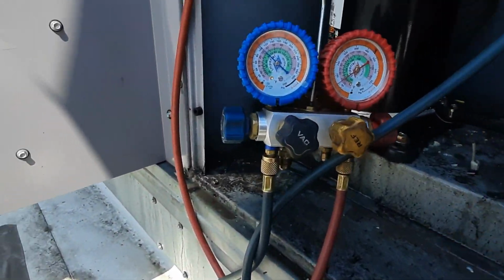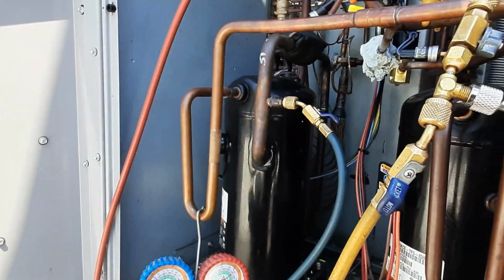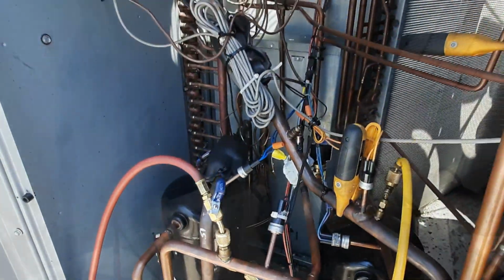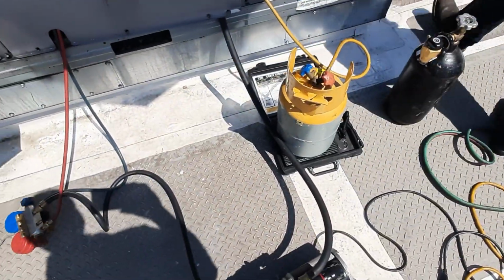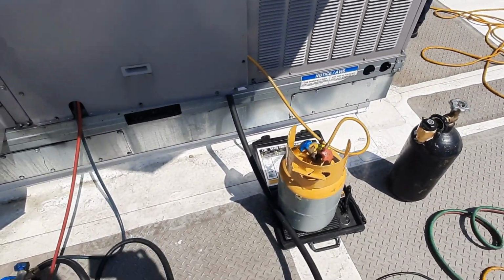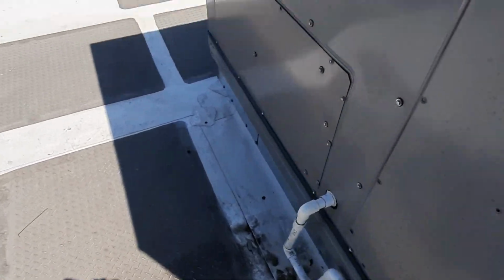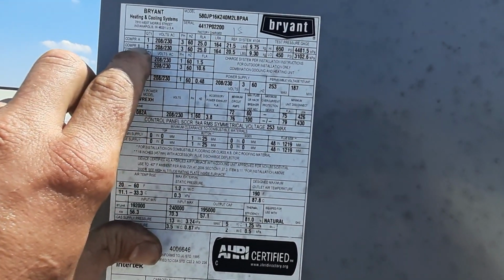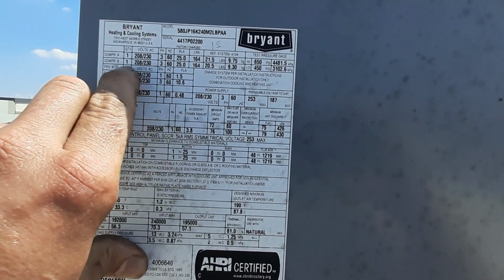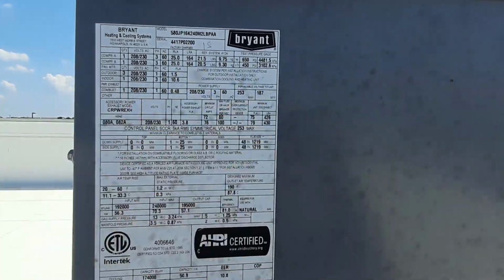We are still holding pressure, a little bit over 100, so we're gonna be good on that guy. We'll get the vacuum set up too. Go ahead and kick a unit back on. I disabled stage 1, stage 2 is plugged back in, so it should run. We're gonna have a 5-minute delay again. So, stage 2, that's the one we're working on, 20.5 pounds.